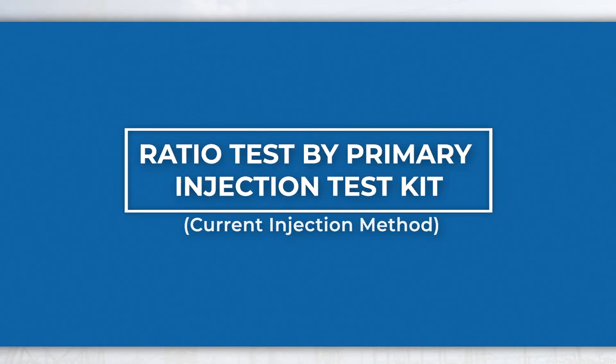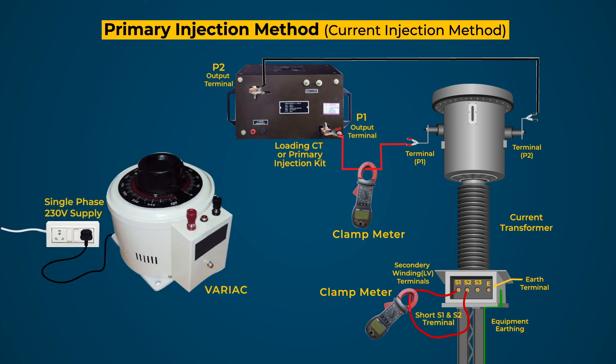The ratio test by primary injection test kit using the current injection method is generally followed in the field. Short both terminals of the secondary winding tap under test and connect the clamp meter. Then connect the primary leads of the test kit to both primary terminals by cable capable of carrying the rated current of the CT, and connect the clamp meter. Connect the single phase 230 V AC supply to the test kit through a variac to get the required current for testing.